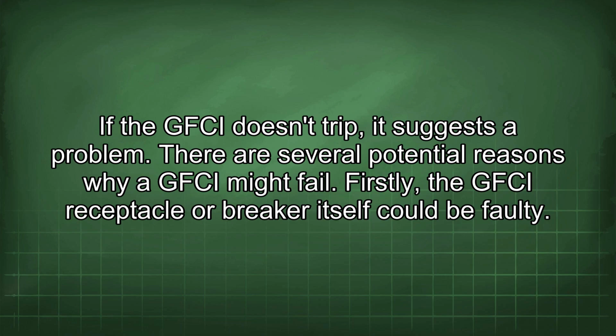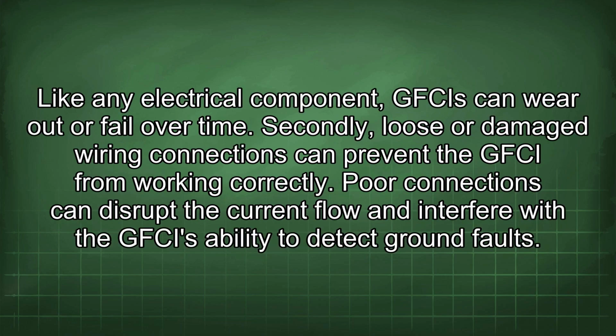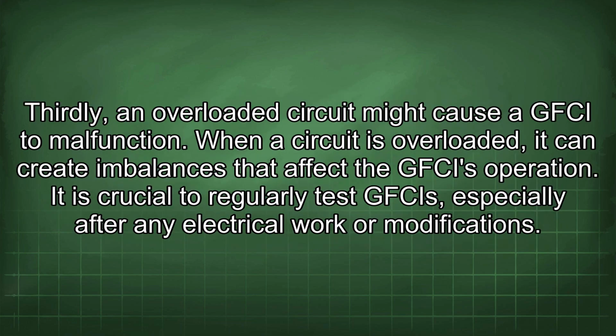There are several potential reasons why a GFCI might fail. Firstly, the GFCI receptacle or breaker itself could be faulty. Like any electrical component, GFCIs can wear out or fail over time. Secondly, loose or damaged wiring connections can prevent the GFCI from working correctly. Poor connections can disrupt the current flow and interfere with the GFCI's ability to detect ground faults. Thirdly, an overloaded circuit might cause a GFCI to malfunction. When a circuit is overloaded, it can create imbalances that affect the GFCI's operation.